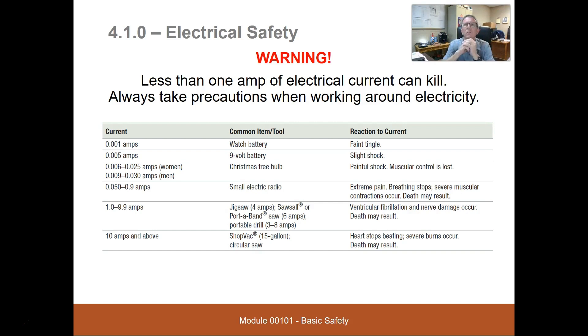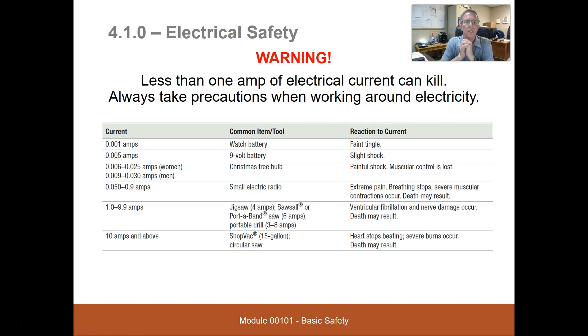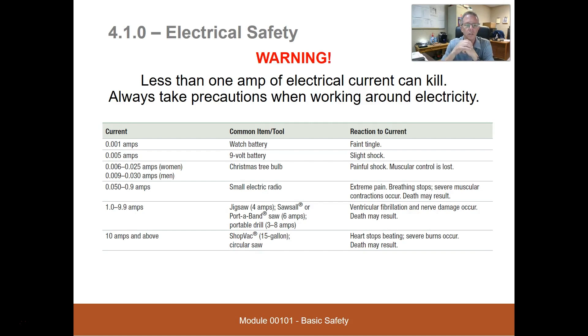Almost every circuit we work on is 15 full amps or higher, so any circuit has a potential of 15,000 times what we're talking about in this chart. One milliamp — one one-thousandth of an amp — would probably give you a faint tingle, like a watch battery. Five milliamps, like a nine-volt battery, is a slight shock. Six to twenty-five milliamps for a woman, nine to thirty for a man — Christmas tree bulb — is a painful shock and muscular control is lost.